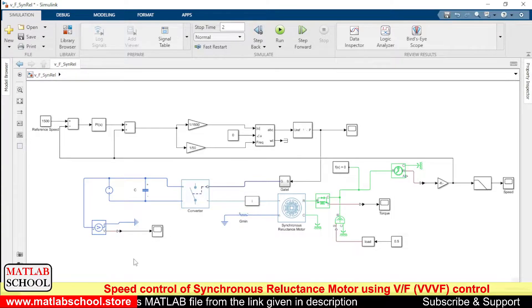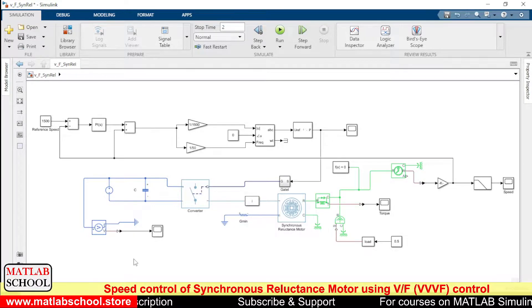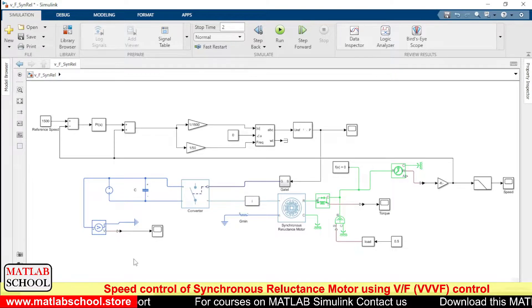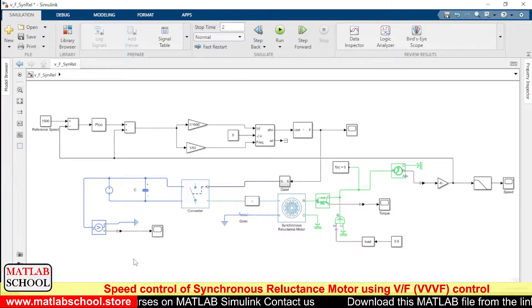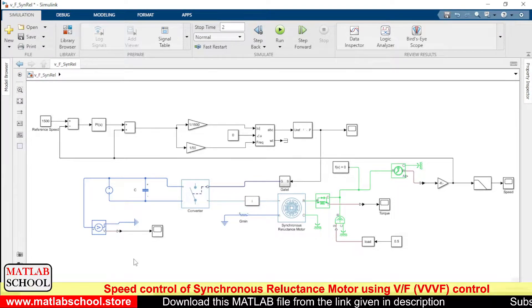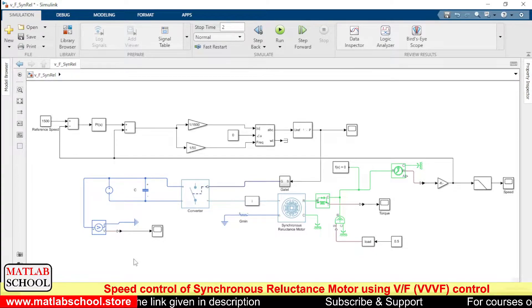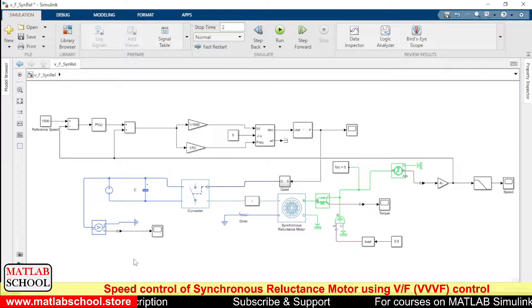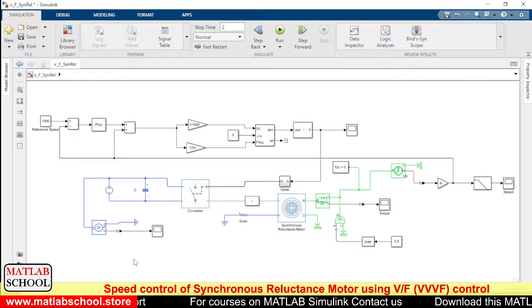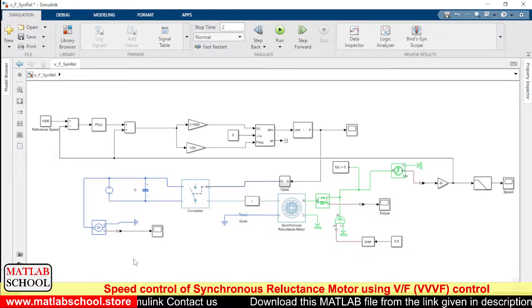As you know, in a synchronous reluctance motor you won't be finding any permanent magnets or coils in the rotor side. Instead you will be finding iron in the rotor side, and the rotation of the rotor is based purely on reluctance. At the stator side we will be finding three-phase windings similar to the coils found in an induction motor or permanent magnet synchronous machine. So the construction difference lies in the rotor side.